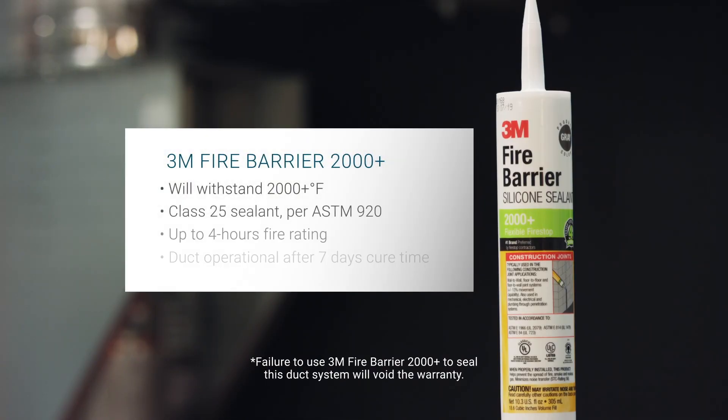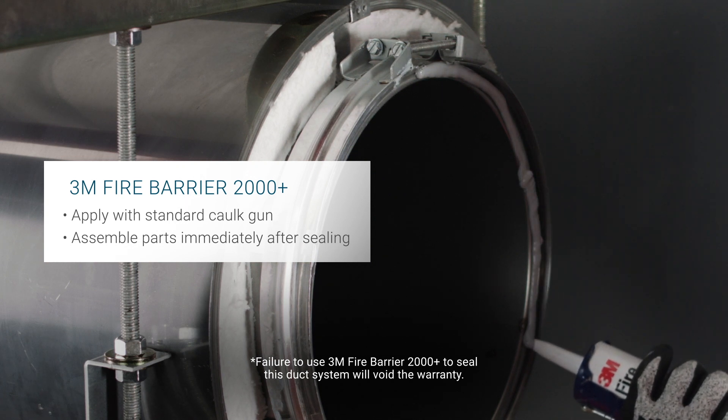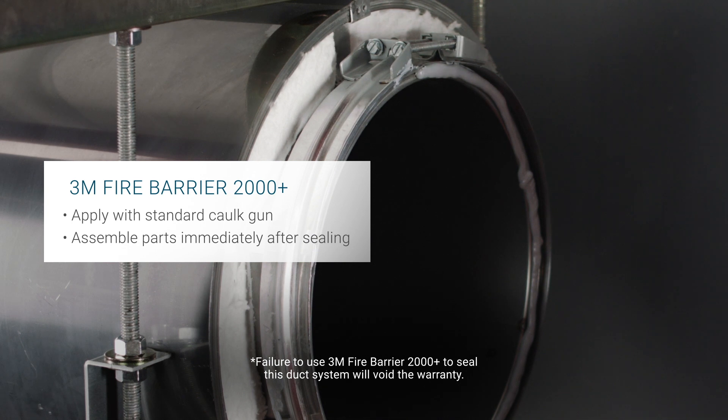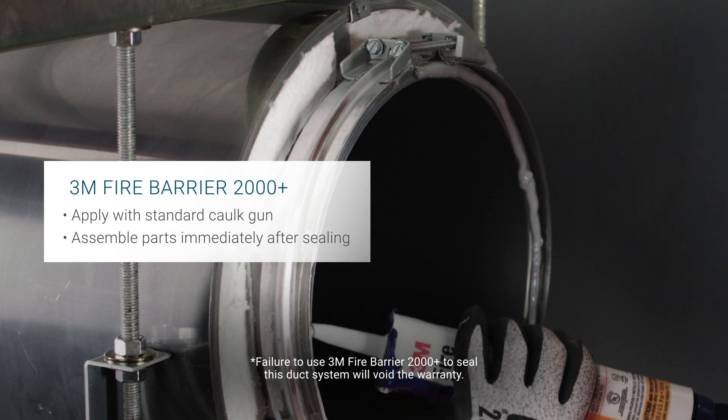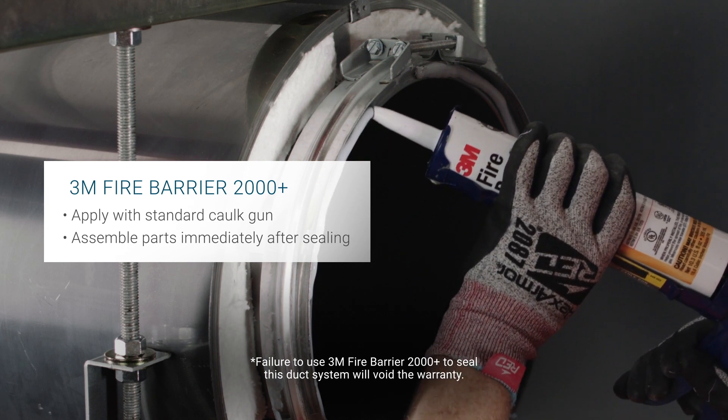Per the listing, 3M Fire Barrier 2000 Plus is the only sealant that may be used to seal this duct system. Sections must be clean, dry, and frost-free before sealing. When installed properly, this sealant will seal a duct system so it is leak-free, and at the same time will control the spread of fire before, during, and after exposure to open flames.